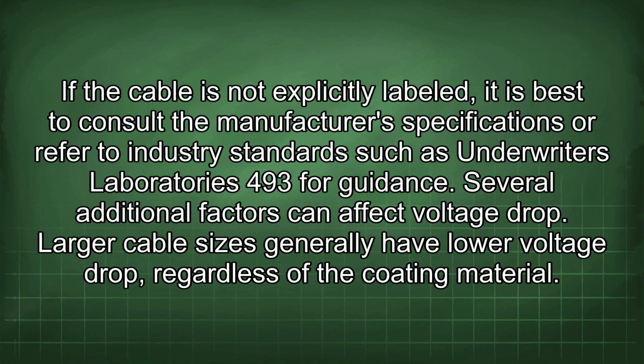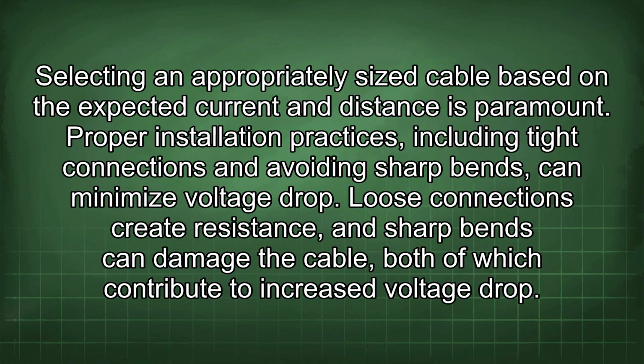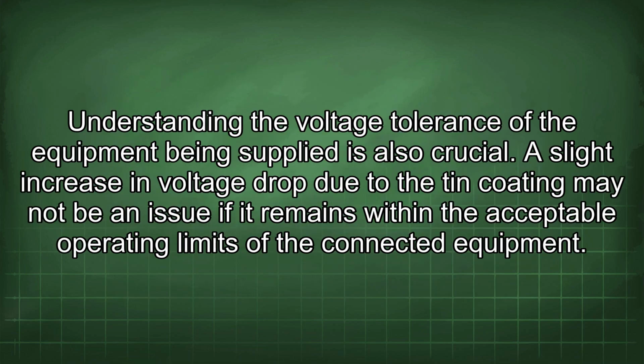Several additional factors can affect voltage drop. Larger cable sizes generally have low voltage drop, regardless of the coating material. Selecting an appropriately sized cable based on the expected current and distance is paramount. Proper installation practices, including tight connections and avoiding sharp bends, can minimize voltage drop. Loose connections create resistance, and sharp bends can damage the cable, both of which contribute to increased voltage drop. Understanding the voltage tolerance of the equipment being supplied is also crucial. A slight increase in voltage drop due to the tin coating may not be an issue if it remains within the acceptable operating limits of the connected equipment.